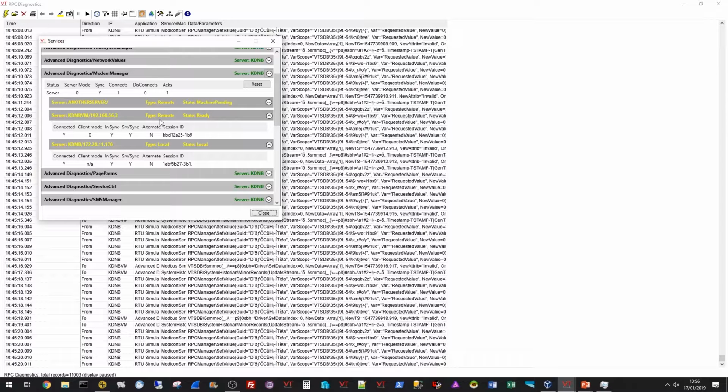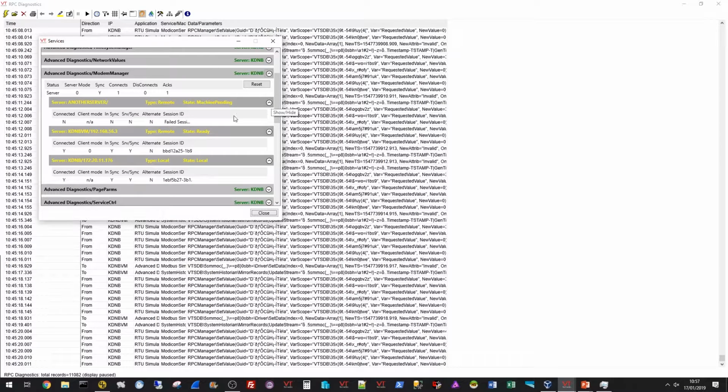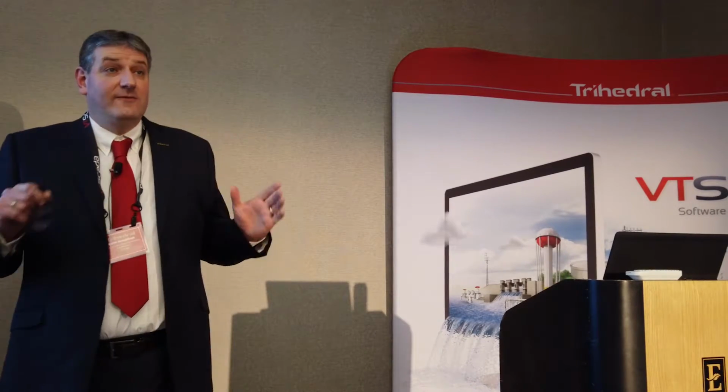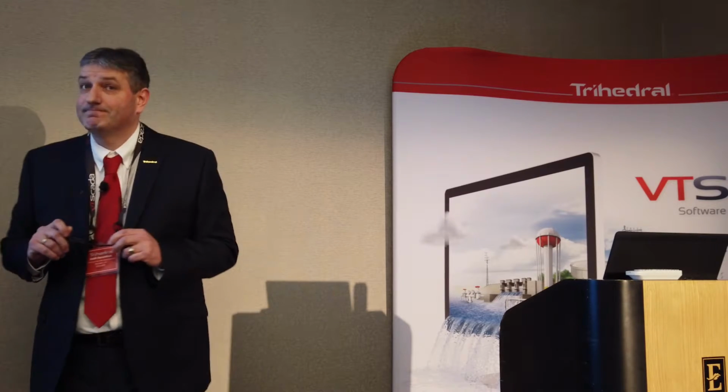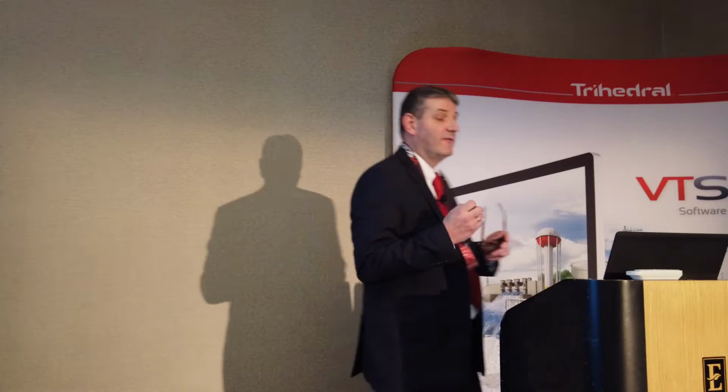Okay? And then because I have added another server, that's the title of the server, into our server list for the application, even though it doesn't exist, VTScada is trying to connect to that server and gather diagnostics for it. So it's saying in there, machine pending, and if I expand that, it actually says it's a failed session ID. It can't establish a connection to that machine. Okay? And all of that information is available for all of the services that exist within VTScada. So at any one time, you can go in there and find out exactly the state of the entire system.